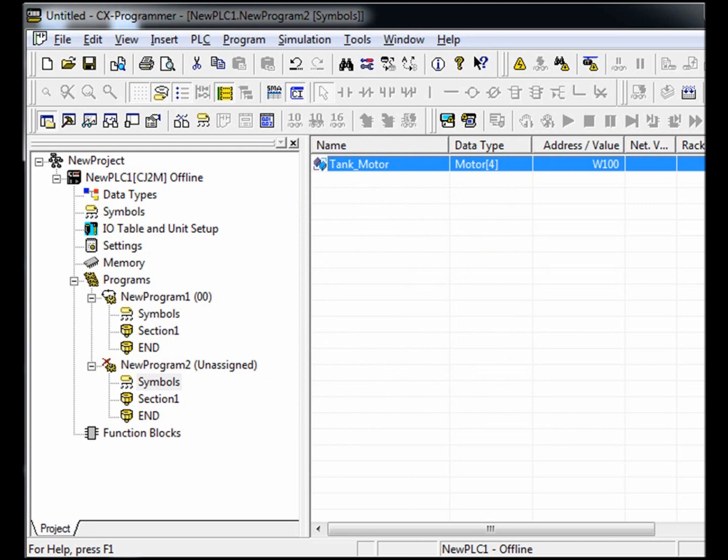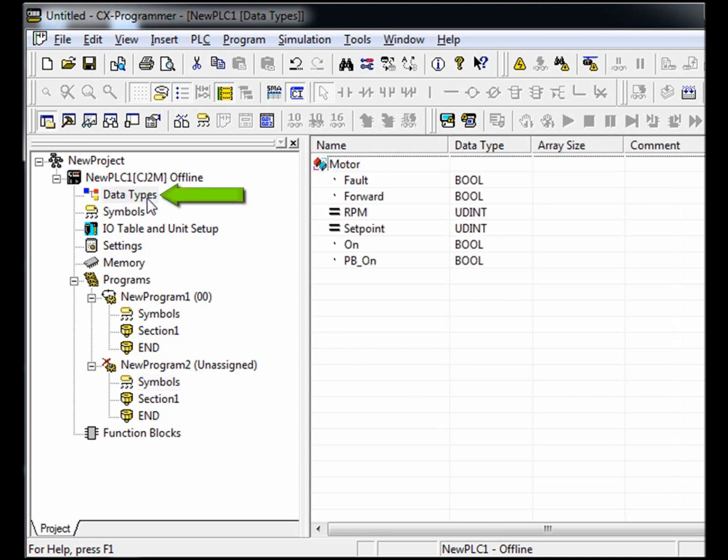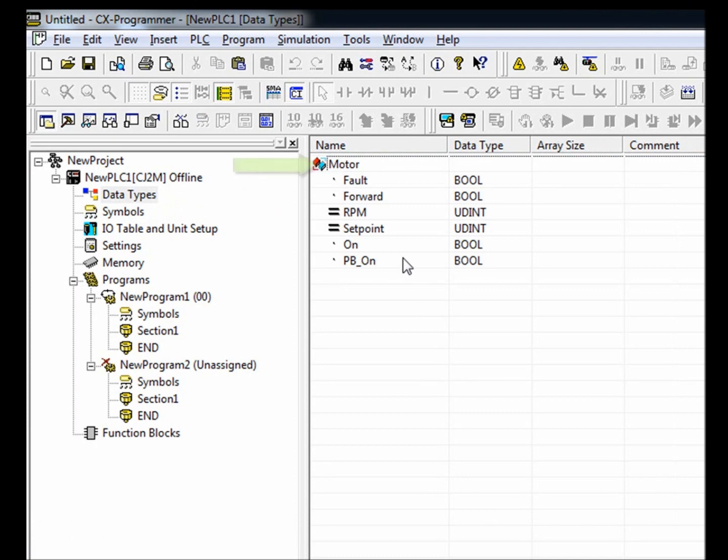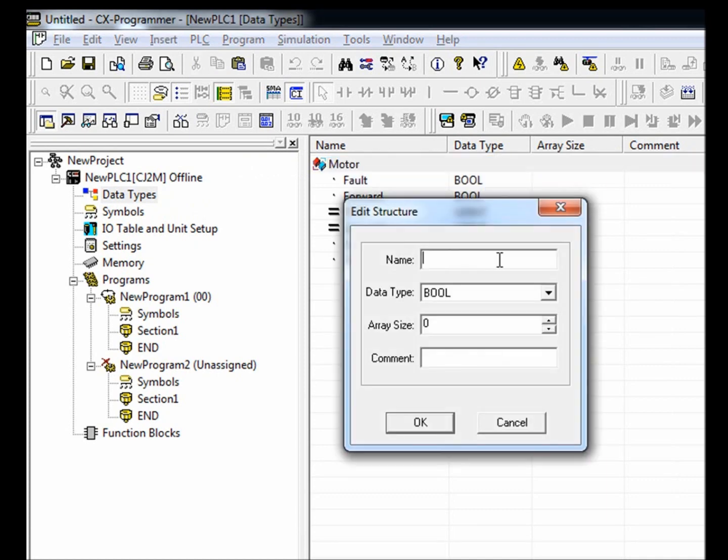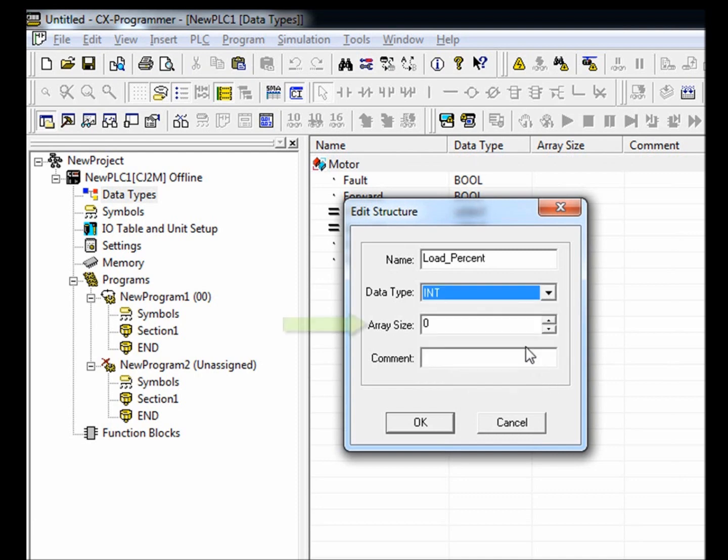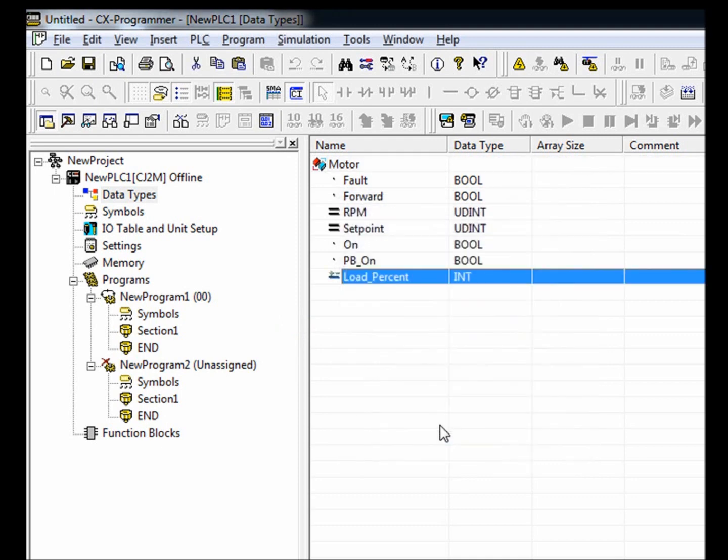If we want to add an attribute to our motors, all we need to do is go back to the data types table, select the data structure called motor, right click, insert, member. I'm going to call this load percent. I'm going to set the data type as an integer. Also notice that each member of a data structure can have its own array size if needed. We just created a new member for our motor data structure called load percent, and now all four motors contain this load percent member.